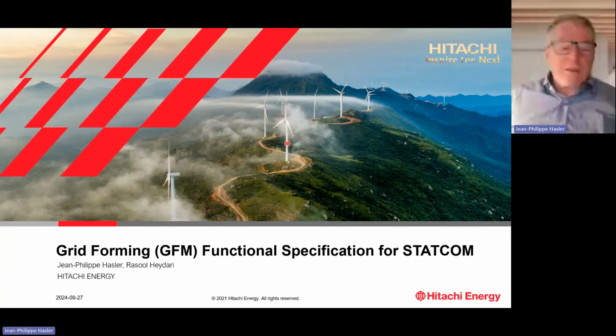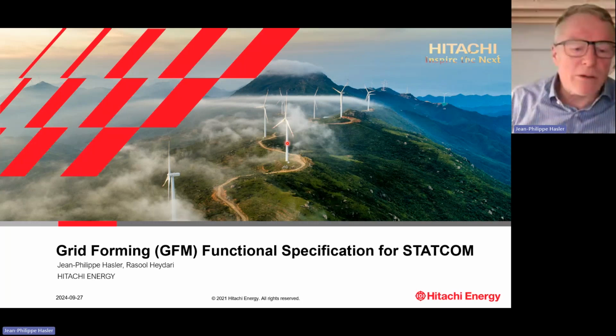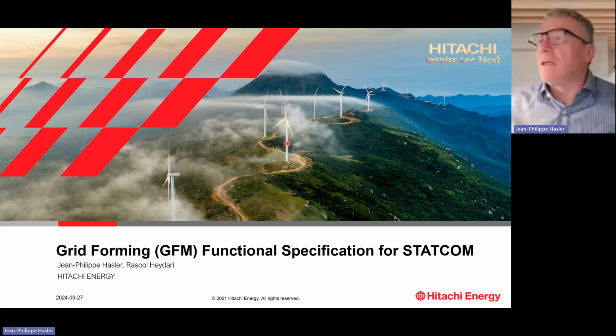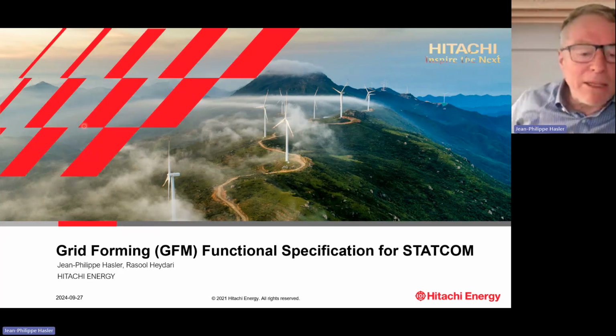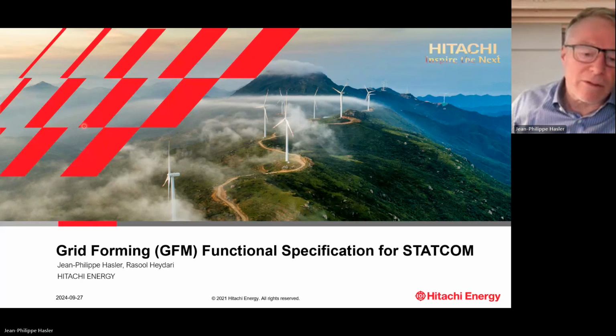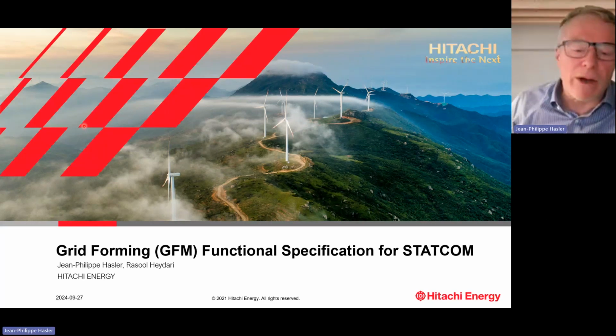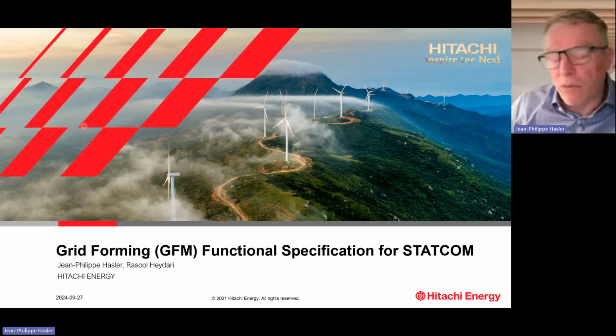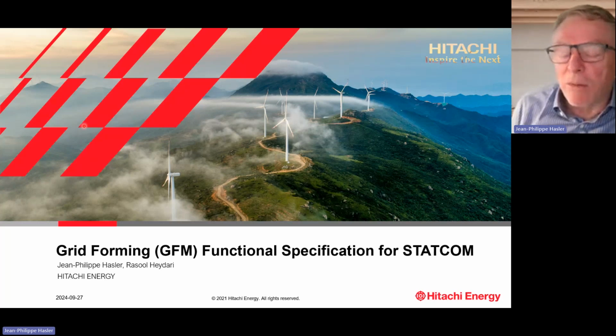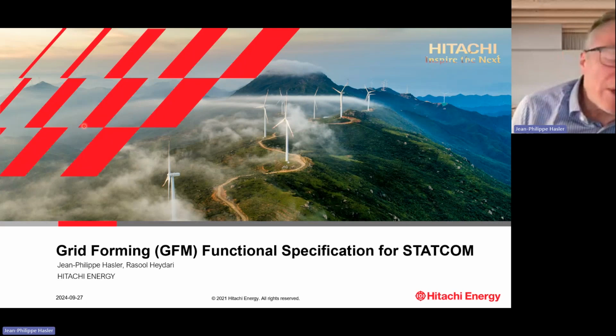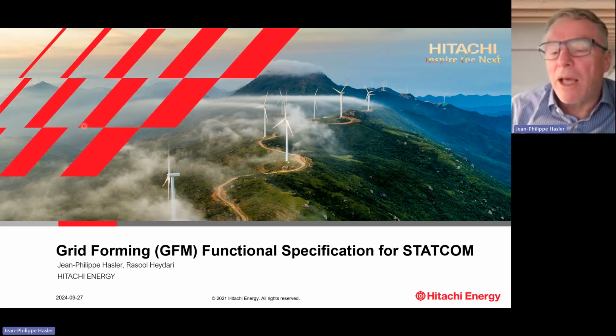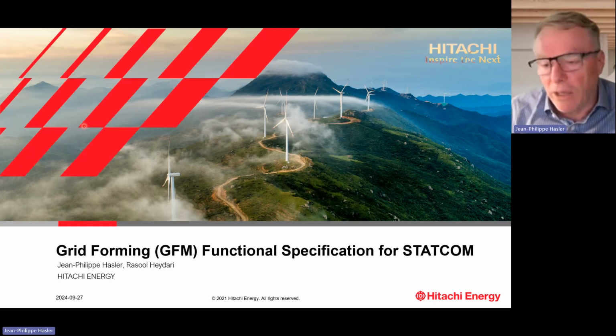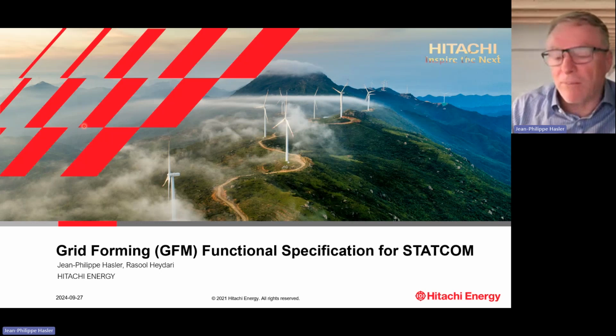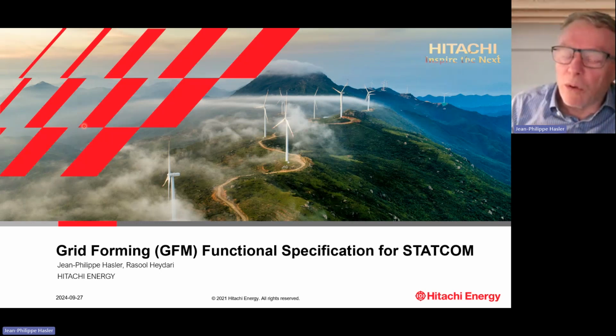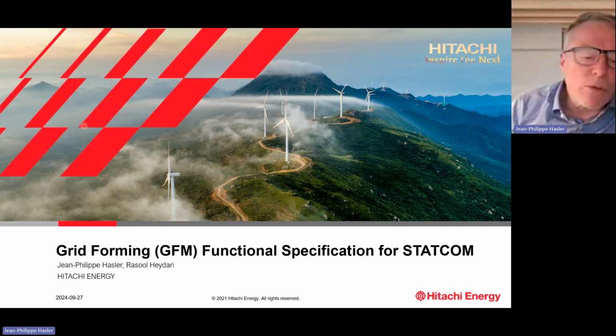So I will present our understanding about the grid forming functional specification for STATCOM. I think probably this grid forming definition you have for IBR means a device which is put in the net to provide energy. It's a bit different probably for a STATCOM. A STATCOM is a device located somewhere in the transmission system and supposed to stabilize the voltage. That was the initial functionality of the STATCOM. And now, of course, it has been extended somehow to not only provide voltage support, but also to support the frequency.